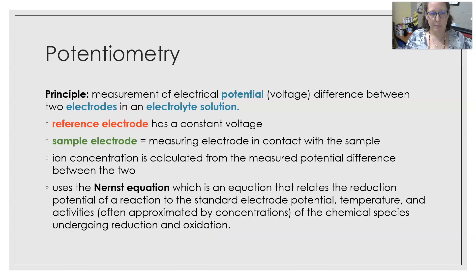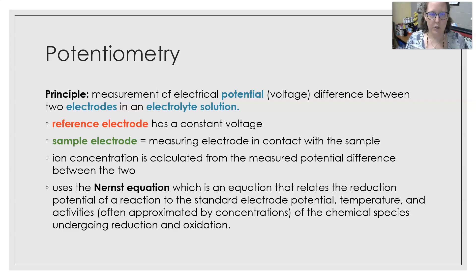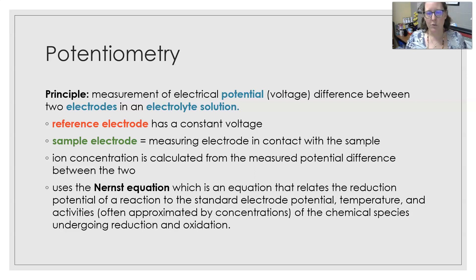The principle of potentiometry is the measurement of electrical potential and voltage difference between two electrodes in an electrolyte solution. The reference electrode has a constant voltage, and the sample electrode is the measuring electrode that is in contact with the sample. The ion concentration is calculated from the measured potential difference between the two electrodes.